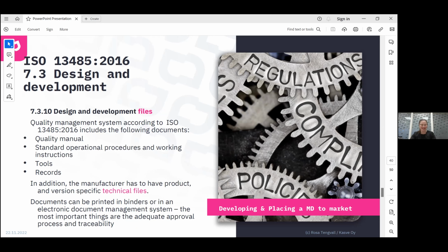From all of this, you will have an extensive amount of documentation, so-called design and development files. If you check the 13485 standard, there are a few documents that are necessary. So the quality manual, and then all the standard operational procedures, so SOPs, where you define how you're going to do this design and development. So the planning. You will have some tools, records, and the technical file set. Technical file is about the product documentation, the specification, the test plans, test reports, risk management file, etc. So there is quite an extensive list of documentation that you need to fulfill during the design and development.